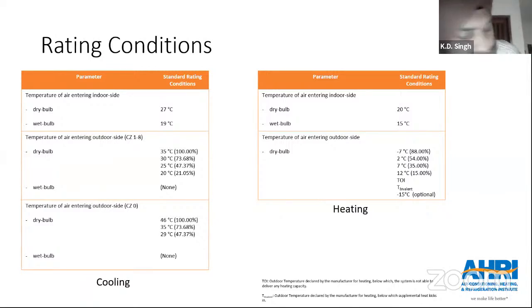If you're building a server room and want accurate control on both temperature and humidity, a VRV will probably have to go through some modifications, or we'll need additional controls to get that. It depends on the kind of server room you're trying to build. For server rooms based only on temperature, VRFs have worked very well - small server rooms, no problem. But for a data center needing closer control on temperature, humidity, and indoor air quality, we might have to move to a higher version of machine that can control both. VRF by itself cannot do this unless we add something from outside with the indoor units, or have an air handling unit with built-in controls. A tailor-made air handling unit with the VRF outdoor unit can possibly do this. But generally, for a data center or room needing close control on temperature and humidity, it's better to go for a precision air conditioning machine. I hope I've answered that.